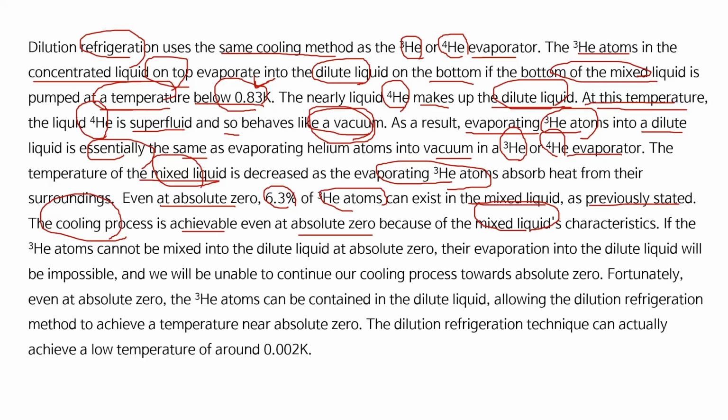If the helium-3 atoms could not be mixed into the dilute liquid at absolute zero, the evaporation into the dilute liquid would be impossible and we would be unable to continue our cooling process toward absolute zero.